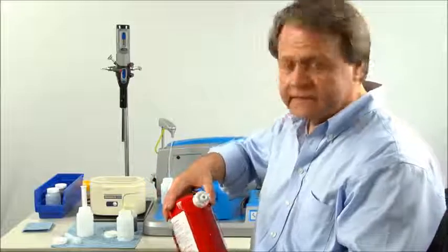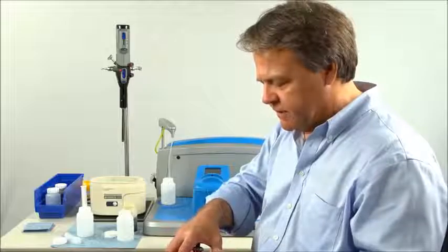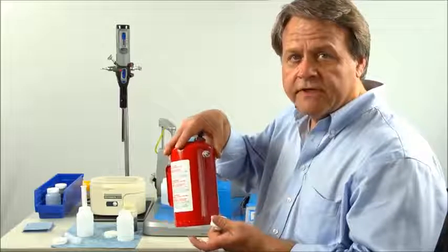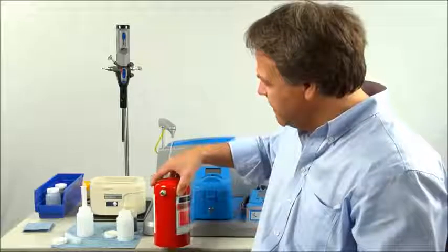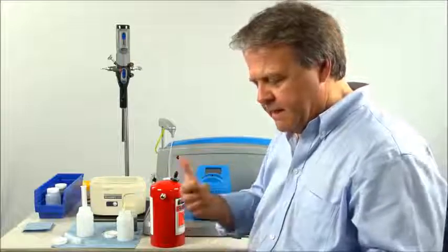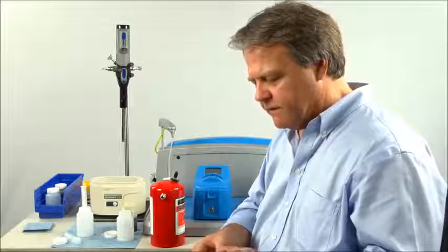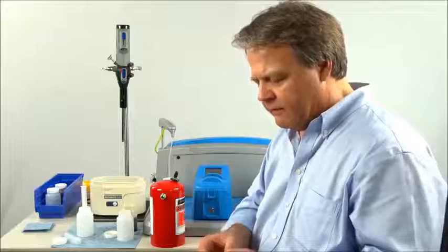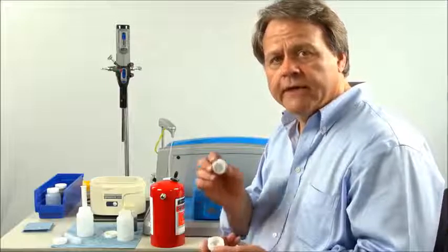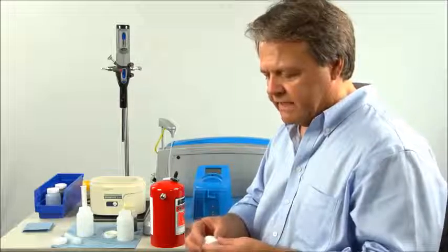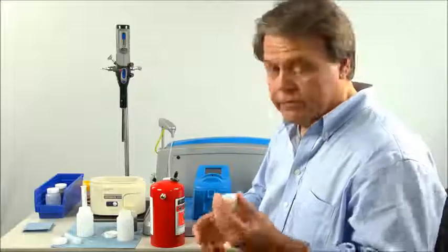One we offer is a standard accessory, solvent filtration. The container is simply filled with solvent, pressurized with a hand pump, and then when it's released, the solvent is pushed through a very fine filter, a 0.8 micron filter, which takes out all particulate above a micron.